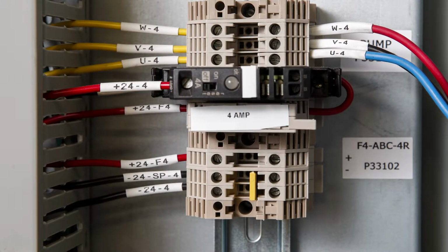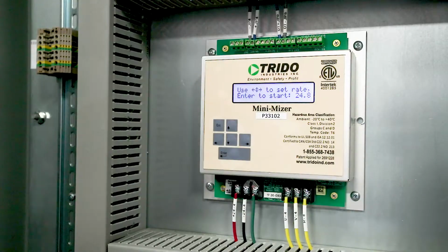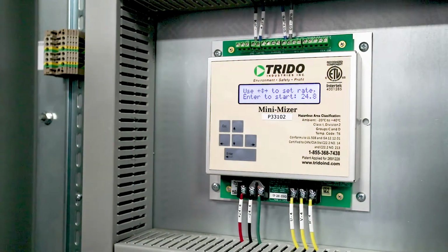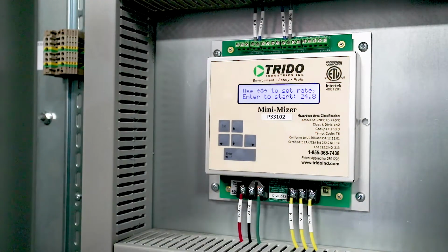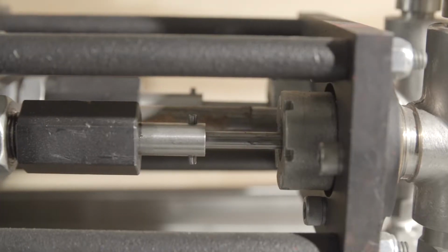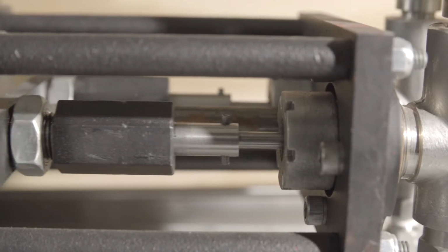Replace the breaker to power up the control panel. Set the actuator stroke rate on the panel to the stroke rate from the spreadsheet. Start the controller and let the pump rate stabilize before starting pump calibration.